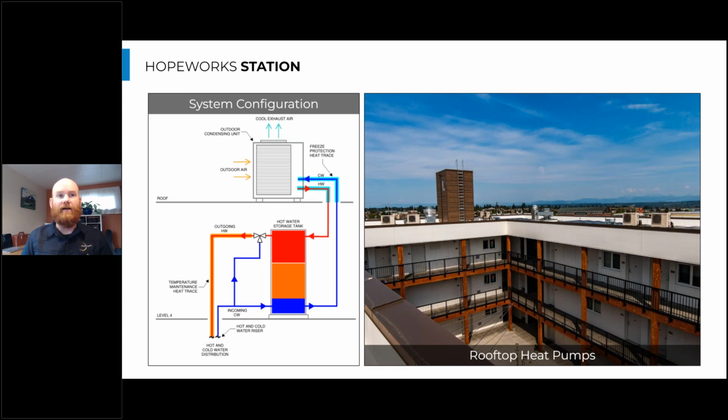We decided as the design team to design around the Sanden heat pump water heating technology, as it's a CO2 based refrigerant, and all that means is it can work in cool ambient air temperatures. So it can work in Washington State even when there's snow on these mountains and when it's 25 degrees outside, right? These are really highly efficient systems that use CO2 as the refrigerant, and those allow us to move heat into water even when it's very cold outside, and it does get cold here in Seattle occasionally.